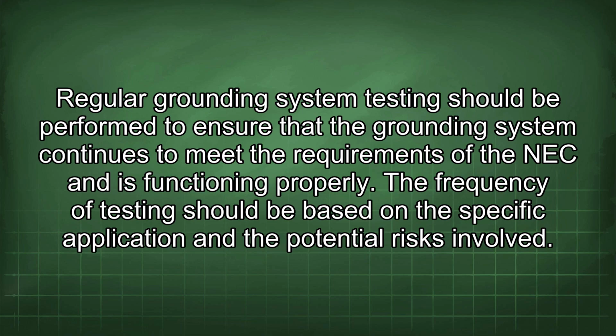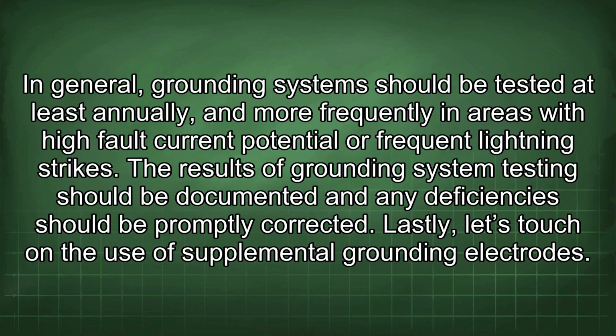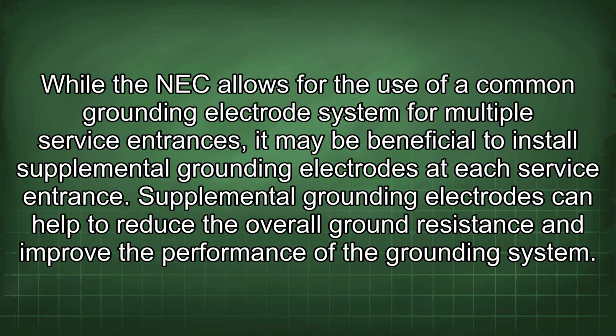The frequency of testing should be based on the specific application and the potential risks involved. In general, grounding systems should be tested at least annually and more frequently in areas with high fault current potential or frequent lightning strikes. The results of grounding system testing should be documented, and any deficiencies should be promptly corrected. Lastly, let's touch on the use of supplemental grounding electrodes. While the NEC allows for the use of a common grounding electrode system for multiple service entrances, it may be beneficial to install supplemental grounding electrodes at each service entrance.